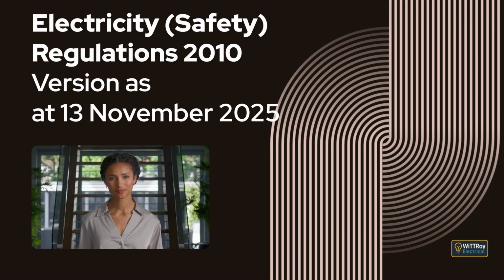Reg 83, Supplier Declaration of Conformity required before sale of declared medium risk articles. This regulation explains that WorkSafe may declare certain low voltage or extra low voltage fittings or appliances to be declared medium risk articles. It explains that these articles must not be sold or supplied unless the New Zealand manufacturer or importer has made a supplier declaration of conformity, or the article is deemed to be approved by WorkSafe and all conditions of that deemed approval are met.